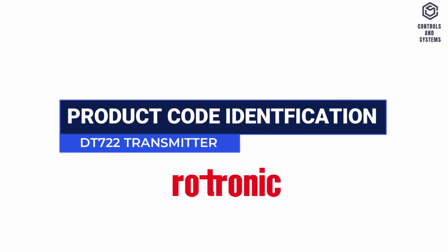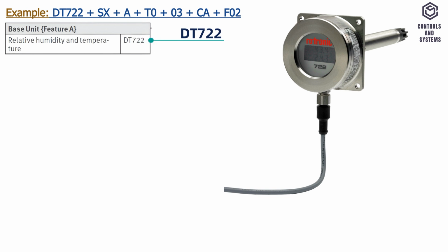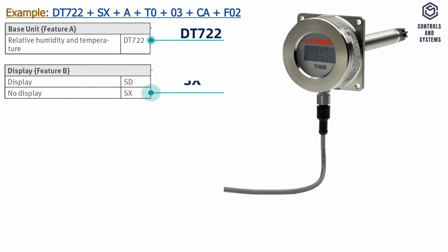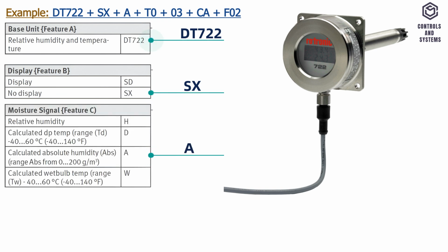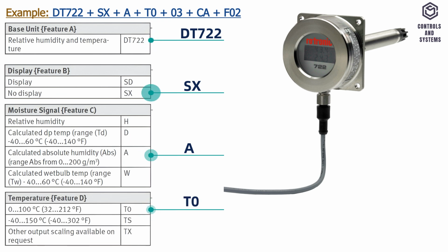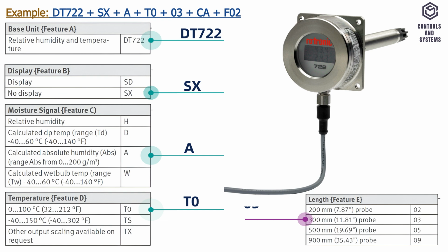Product code identification. The first 2 letters and 3 digits denote a base unit, which includes relative humidity and temperature. The next 2 letters denote the display choice, if SX means no display option. The next letter denotes the moisture output signal and range, if A means calculated absolute humidity. The next 1 letter and 1 digit denotes the temperature output signal and range, if T0 means 0 to 100 degrees Celsius. The next 2 digits denote the probe length, if 03 means 300 mm probe.